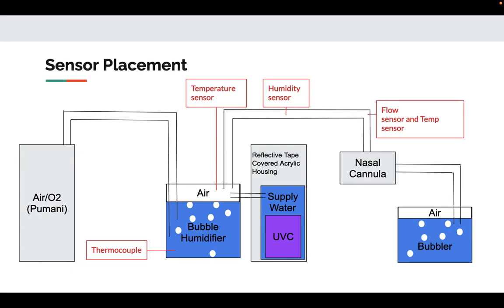So this shows our sensor placement. The thermocouple and the bubble humidifier will shut off after a certain temperature is reached. A temperature sensor regulates that. There is a humidity sensor coming out of the bubbler humidifier, and then a flow sensor right before the nasal cannula to understand what flow is being sent directly to the infant.